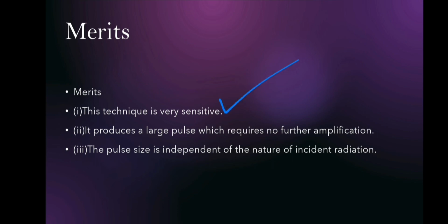This technique is very sensitive, and it produces a large pulse which requires no further amplification. And the last thing is the pulse size is independent of the nature of incident radiation. No matter which radiation you use, the pulse size is independent of the nature of the incoming radiation.